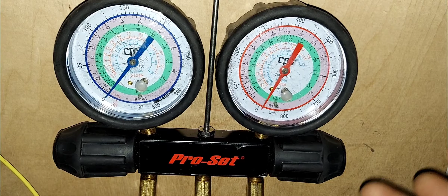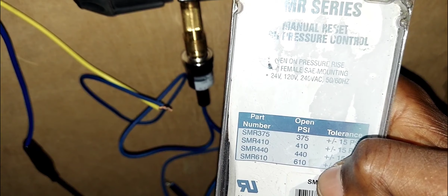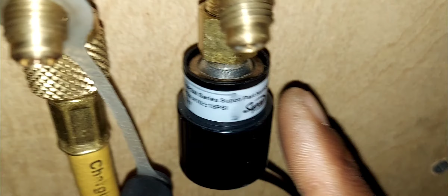All right. As a matter of fact, this is the box for the high pressure switch, and the version I'm using right now is the SMR410. If this was an R410A system, we would be using this switch right here, 610 psi. Okay, so yeah, again, this is not really set in stone. Different manufacturers might choose to make a special switch just for their equipment. What you do, guys, when you have a situation like this, you want to know what your switch is capable of handling, what's the cutout or cut-in point. It's going to be on here. It's going to be written on the device. All right, so that's it. That's how you solve that problem.